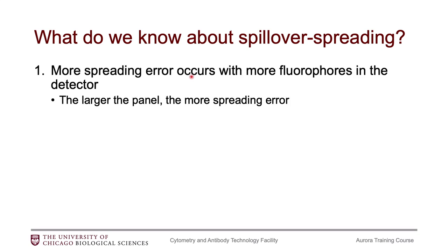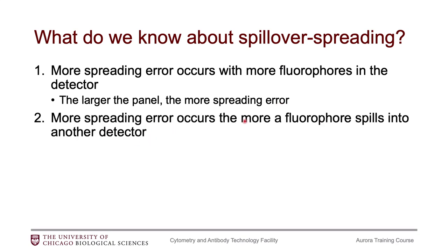The first rule is that more spreading error occurs when you have more fluorophores in the detector — that translates to the larger the panel, the more spreading error potential you have. This is why we need to pay attention to spreading error much more on the Aurora. Most people who have jumped over to the Aurora are looking to do very large panels. If you are looking to just do a 10 or 15 marker panel on the Aurora, you're going to have the same amount of spreading error issues as you would on a Fortessa. But as we increase the size, we have to pay attention to this spreading error. The second rule is that more spreading error occurs the more a fluorophore spills into another detector.